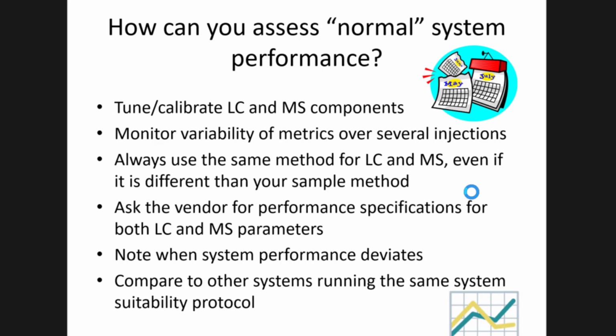You have to baby them. You have to make sure your solvents are fresh and degassed. Don't underestimate the effect that that will have. I was involved in a study last year where we weren't getting reproducible system performance when evaluating a new piece of technology. And of course, we blamed that technology and not the LC. And when we went back and said, oh no, we have to prime, use degassed solvents, purge, flush the system, measure the flow rate, oh my gosh, now everything is working, imagine that. So don't underestimate making sure your LC is working well.